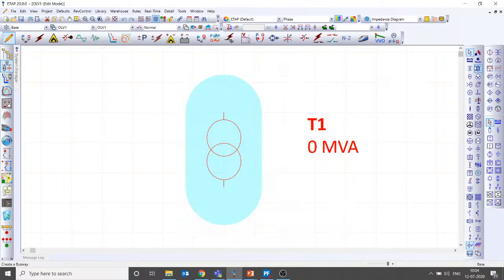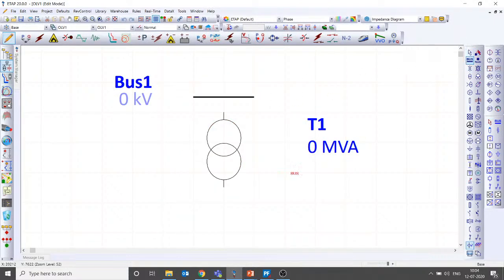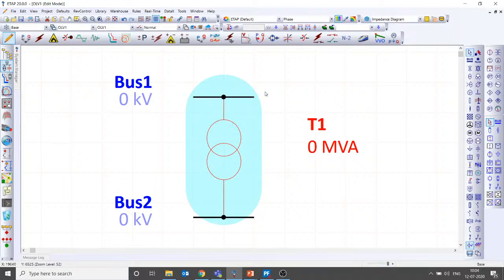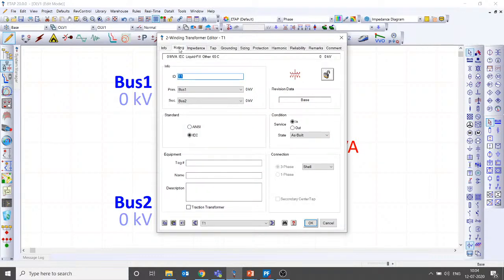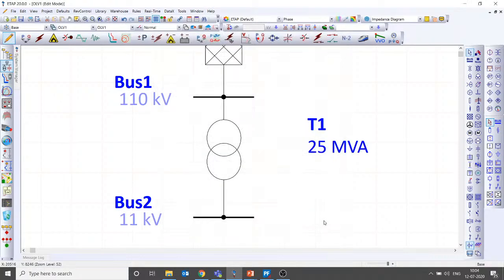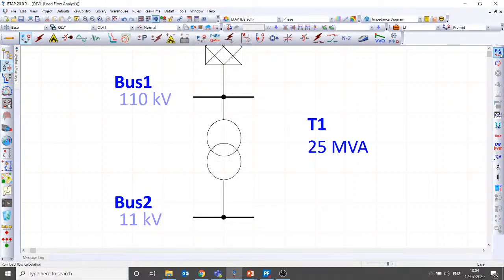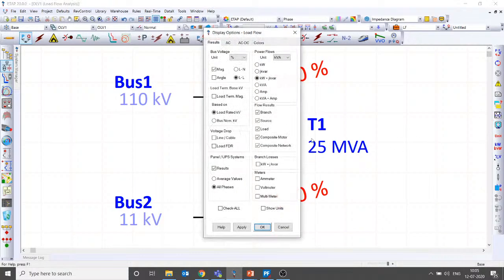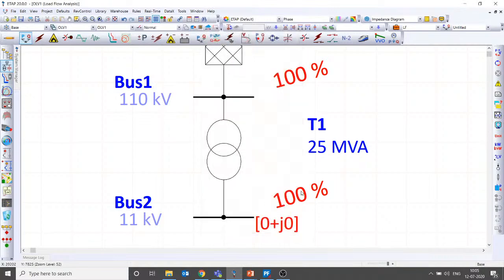Let me quickly go to an example. I will try to simulate this in both simulation software, ETAP and DIgSILENT PowerFactory, and see how the results change. So I have a 110 kV, 11 kV transformer. I'm just giving a 25 MVA transformer with a typical impedance. I'm trying to focus only on the no load loss. The transformer is now without any loads, so there are no losses here. If you display the branch loss, it is 0 kW and 0 kVAR, and let's show the units as well. So the loss is 0.